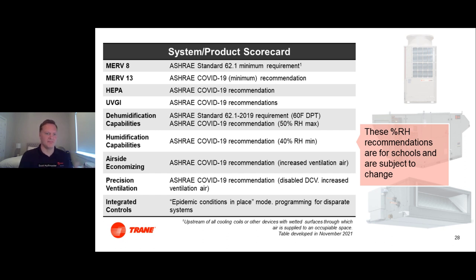MERV 8 is a baseline. That's a standard 62.1 requirement for any coil that has a wetted surface. You might be surprised to know there are systems that are put in today that at times are not even using a MERV 8 filter. And that shouldn't be happening. If you're doing a system that can't do a MERV 8, you need to decouple your sensible and latent loads so that you're not creating a wetted coil in those systems. MERV 13 is a very core recommendation. We hear it all the time. We've heard it throughout the pandemic, but not all systems can handle MERV 13 pressure drop. HEPA, yeah, HEPA is great. But again, can your system handle that pressure drop?